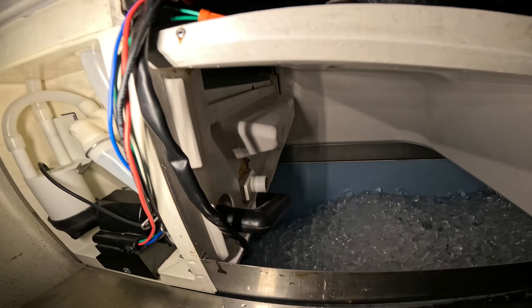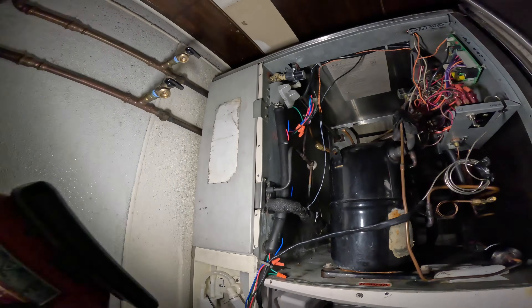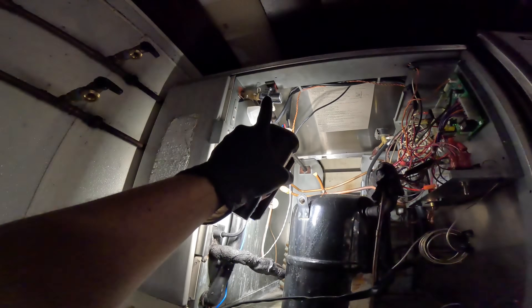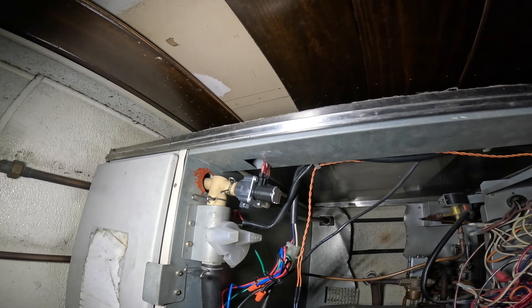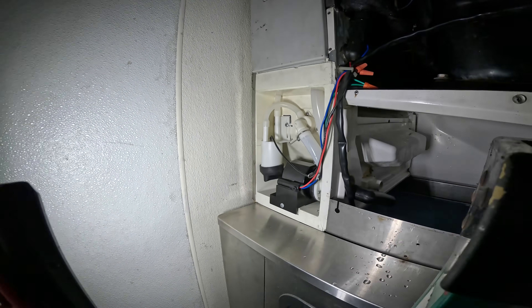Power off, water drained — you don't have to worry about water coming in, you don't have to cut it off because it's feeding this unit as well. There's a solenoid here — it's your water inlet valve, basically a solenoid valve. It's closed when you're not applying power, so that's taken care of.